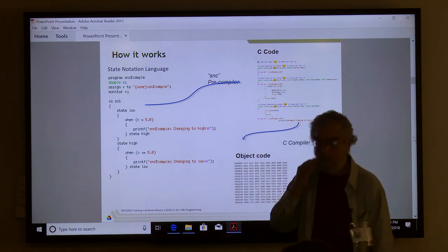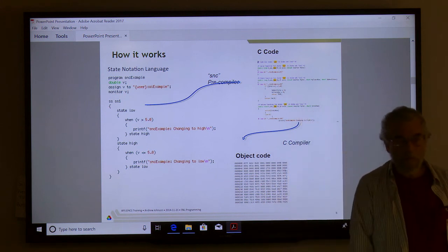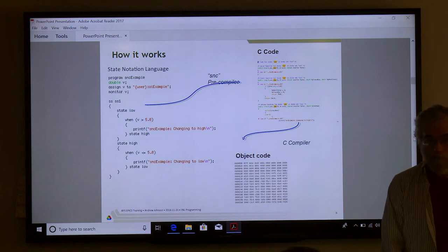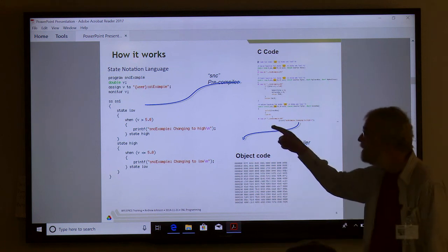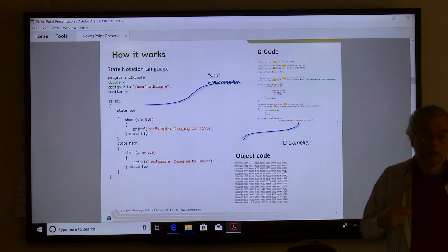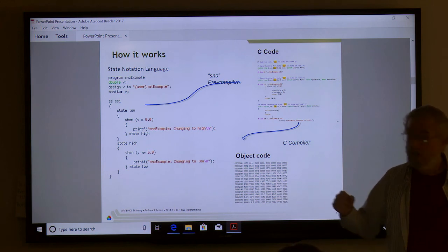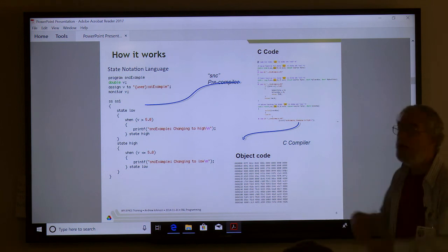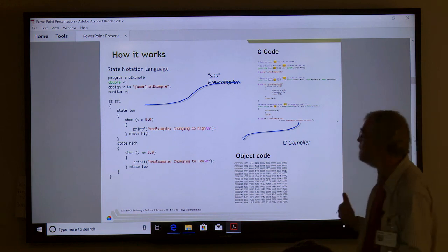When you say monitor a certain PV, how do you know with which frequency you do it? Oh, it's already set for this one. In this case, monitor means put a channel access monitor on that, so we're going to get an event whenever that thing changes value outside of its MDEL, its monitor delta field. Okay. So somebody else is in charge of sending us those events.